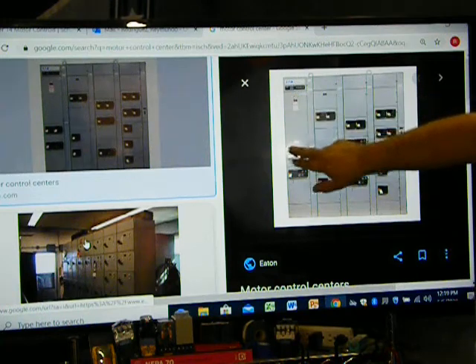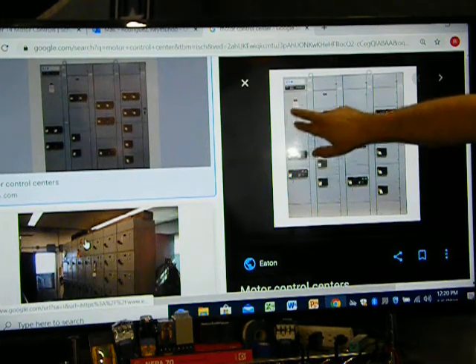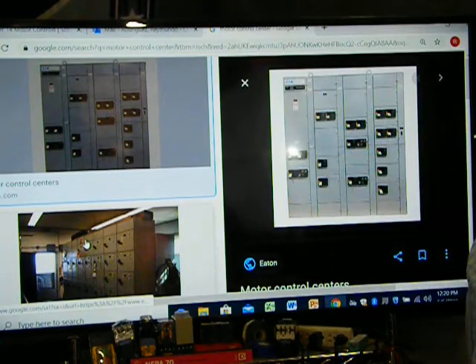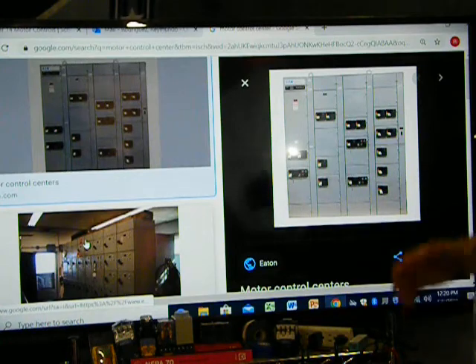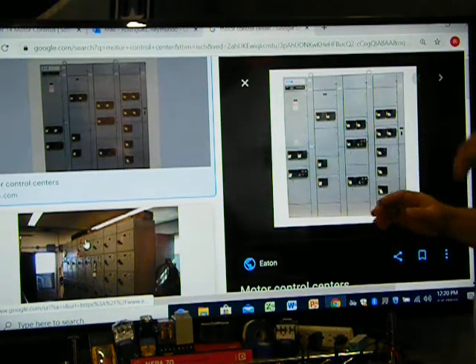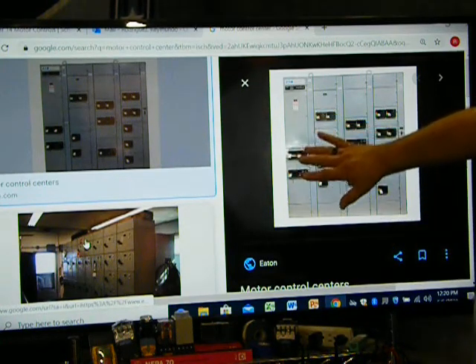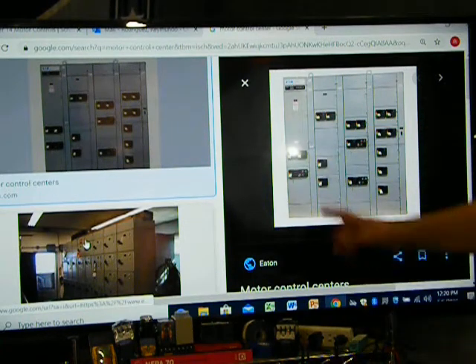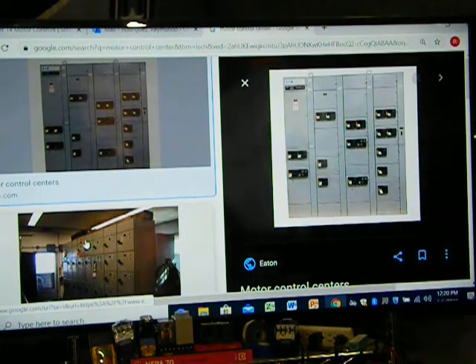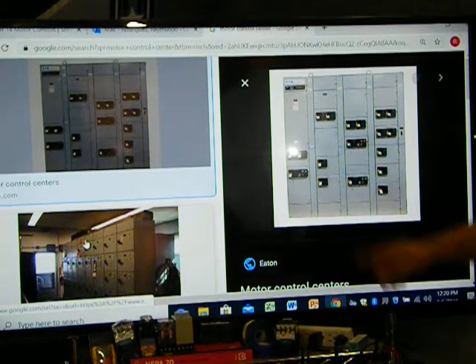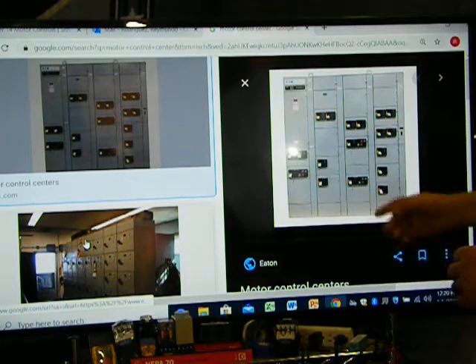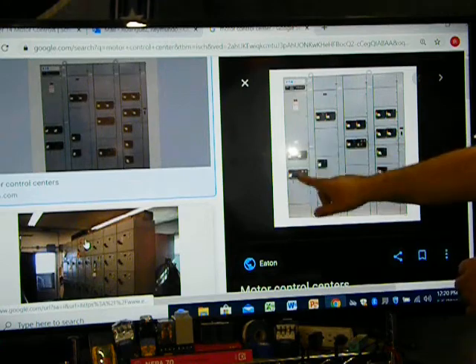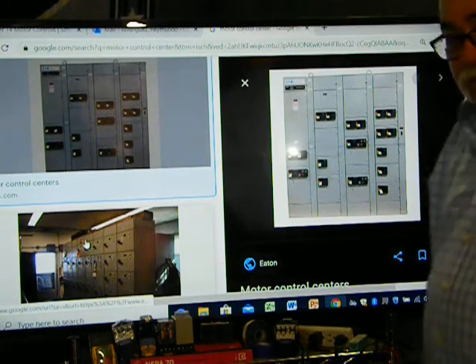I've seen some where they'll have an area and a panel where they're also feeding receptacles and lighting in a certain room. So we have a fan room. They bring power into the fan room. All the power for that fan room comes out of the MCC. The lighting and the receptacles come out of the breakers. Small exhaust fans or small motors that are always going to be on, 120 volt, 4 or 5 amps, they'll come off the panel. But this is an MCC. These are called individual buckets. These are the buckets.